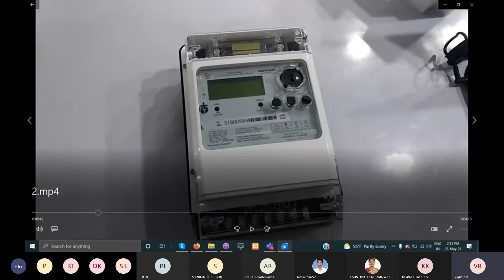So here you can see, this is the optical port. By utilizing this optical port, we can use an optical probe to read the energy data from this L&T meter. These are the up and down buttons to change the parameter view by increment and decrement. And the last one is the reset button. To reset our meter, we have a small push button inside this rubber bush. Once we click that, all the settings get reset. So this is a small thing.